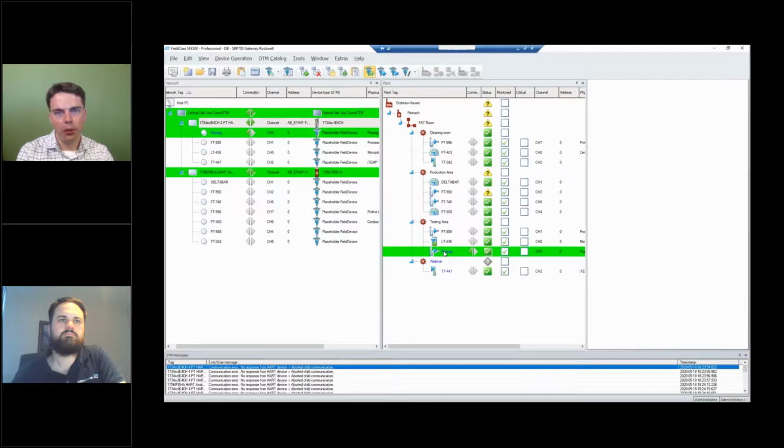We can go through Profibus remote IOs, for instance, because this is an open standard and open protocol. So wherever there are open protocols in place or the vendors are cooperative with us, we can do that. But a Siemens S300, S400, we cannot go through. But if there's a Profibus DP below, or if there's Profinet with HART, we can do that.